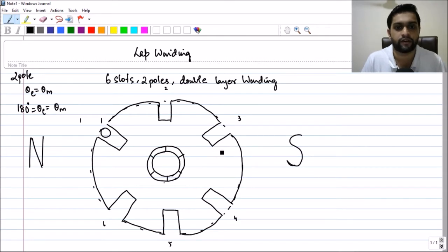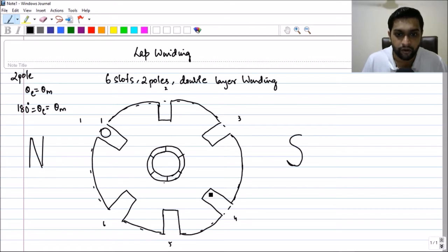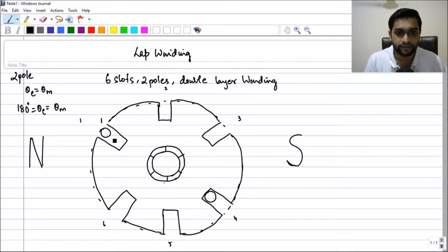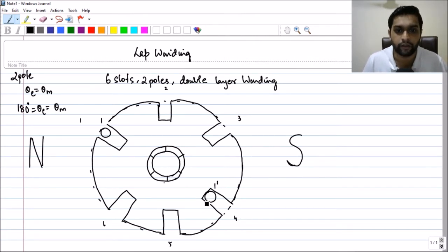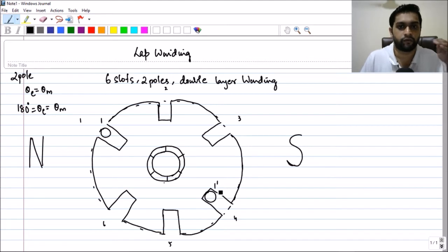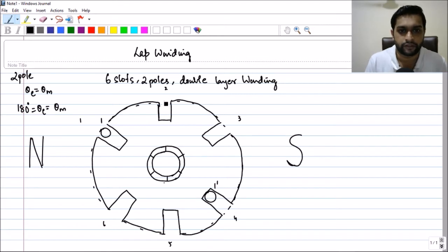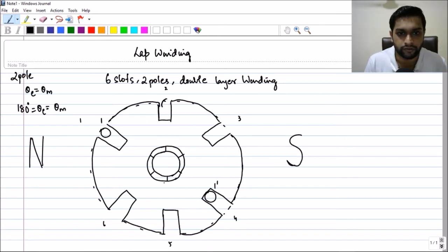This is coil number one. The next coil side for coil number one, which is one-dash, will occupy the bottom position 180 degrees away — which is the fourth slot. So one-dash occupies the bottom position. If one coil side occupies the top position, the next coil side occupies the bottom position. Coil two's top side is labeled two, and its bottom side is two-dash.